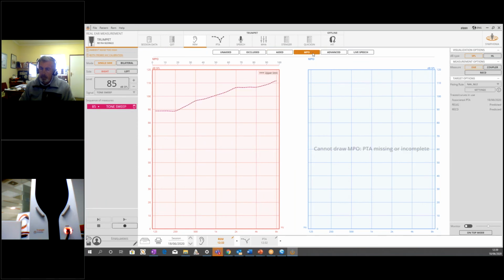Maximum power output, as I told you before, is the maximum power output provided by the fitting rule. Even this time, the speaker will deliver a nice sound of 85 dB SPL. It is very important that the curve acquired for the patient under test does not exceed the dash curve on the screen. Okay, even this time the patient must wear the hearing aid and the hearing aid is turned on.